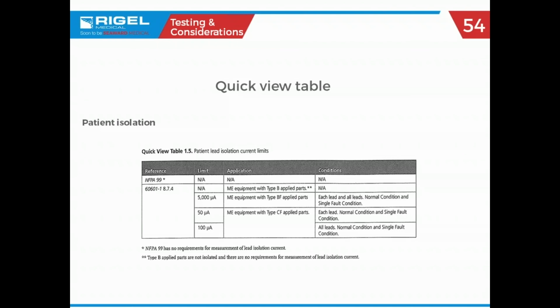So, I have a manufacturer that recommends insulation testing, but they don't recommend a high pot, but they do recommend a Megger. Is there a voltage requirement for the Megger that they recommend? I heard 500 volts DC, and not to exceed 2 megs. I mean, to be above 2 megs. Right. So when you're doing isolation testing, you're really looking at it kind of like a breakdown resistance, right? So that's why it's above 2 meg. The manufacturer should specify what voltage they want that done at.